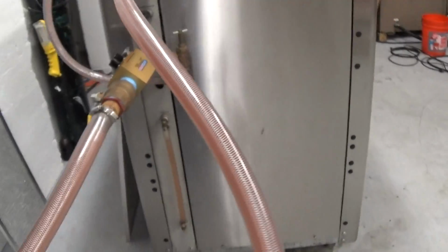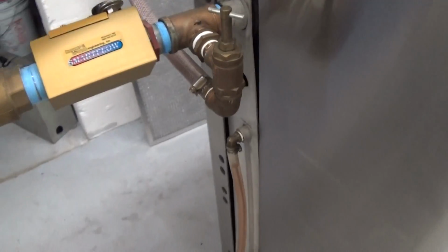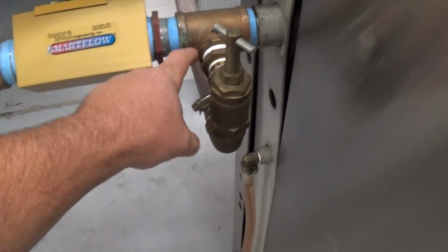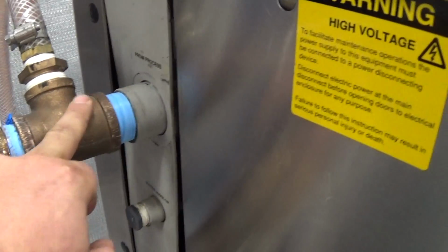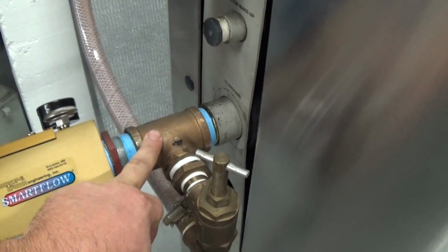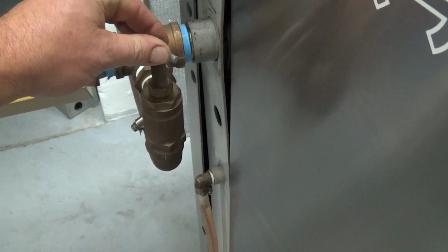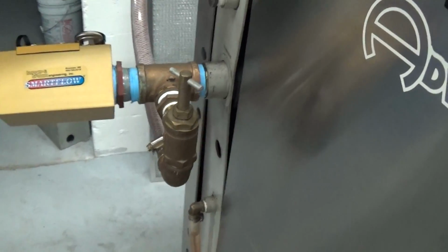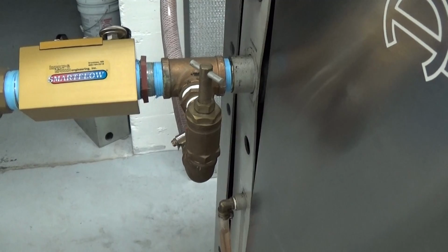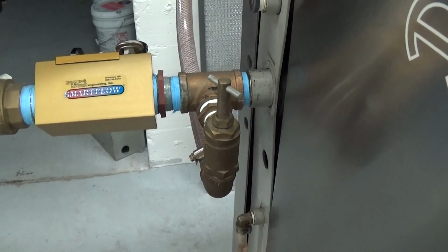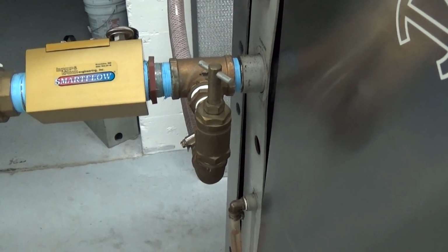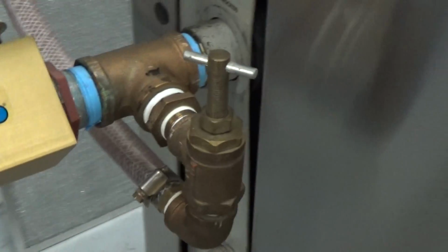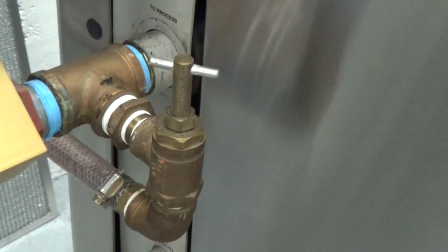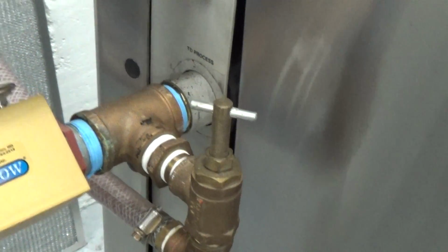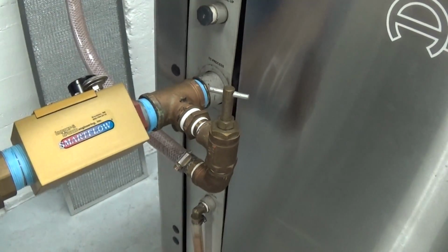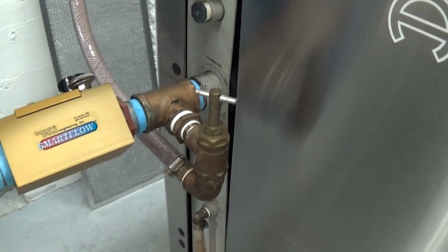All chillers should have a bypass, and I believe this one's going to ship with us here. We have the T on the from process connection and the to process connection, and we have this manual adjustable bypass. If you're starting out small and your lines are much smaller, say ½ inch or something like that, which is on the small side, this is a case where you have this open so you can satisfy some flow requirements over the heat exchanger. Otherwise, it'd be a little bit too restrictive and you'd go into low pressure alarm.